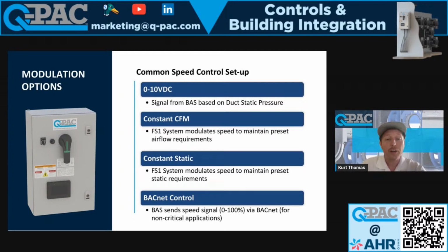All right, so in auto mode, there are 4 different ways to control the speed of our fans. So 4 different speed controls. One is a 0 to 10 VDC, right? I think most people are familiar with that. That is the most common. I would say that our fans are controlled through that 0 to 10 at least 90% of the time. So the standard setup is for your controls contractor and your building automation system to monitor the static pressure 2/3 the way down the ductwork. And then they just modulate that 0 to 10 volt signal that they send to our fans to ramp them up and down to make sure they're maintaining that duct static pressure. That's the most common use.